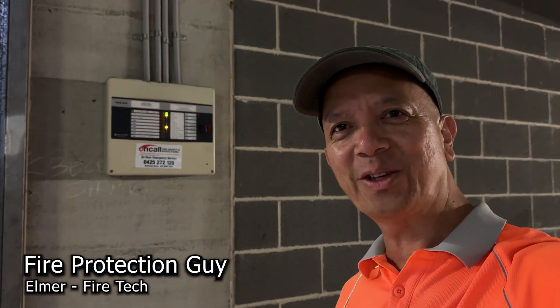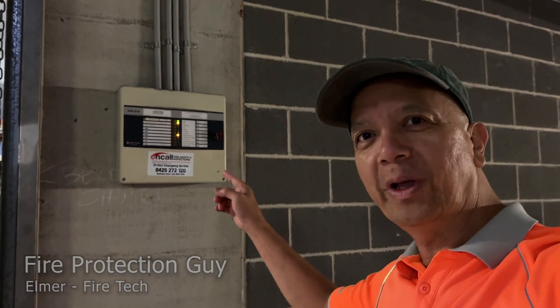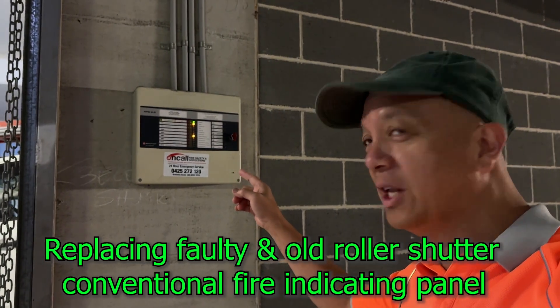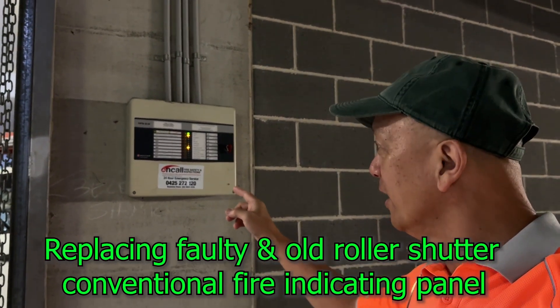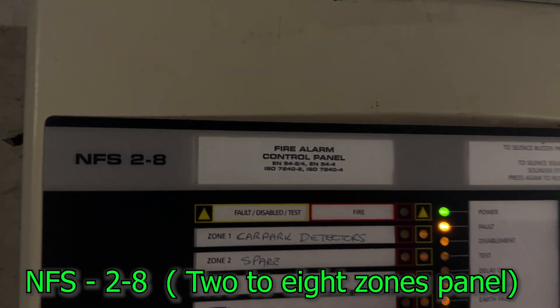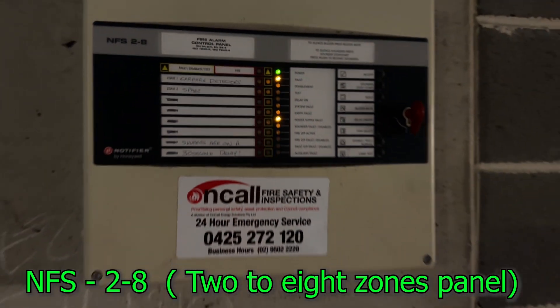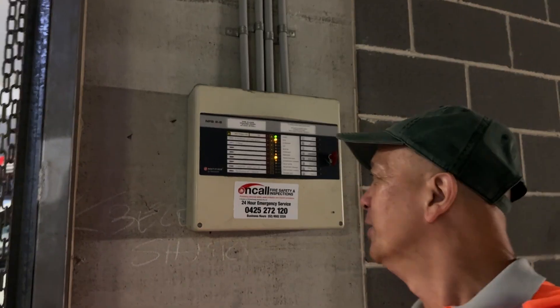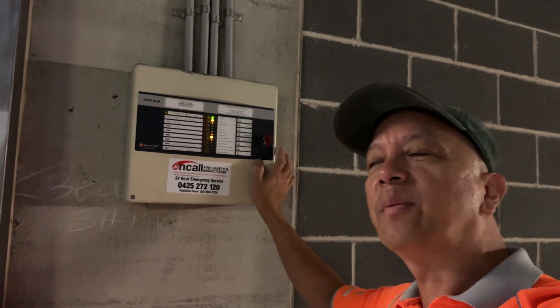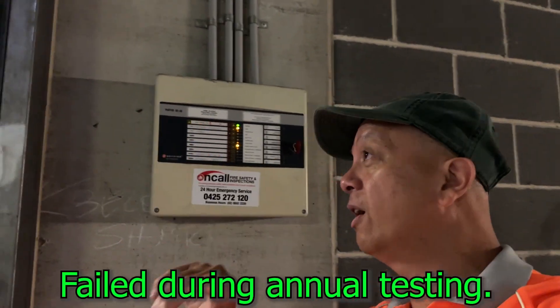Hi guys, Elmer your fire protection guy. We're going to replace this old conventional fire panel, the NFS 2-8. The problem in this fire panel is that all the detectors are not operating. It's a zone card problem. There is no power in the conventional zone circuit.